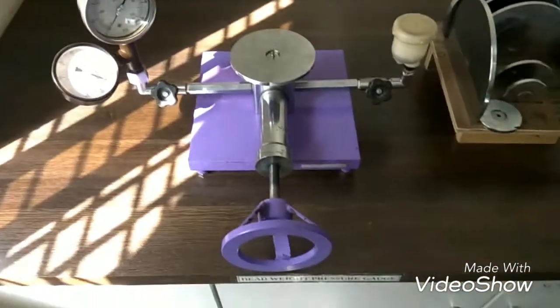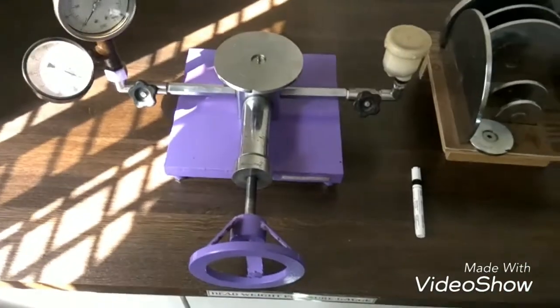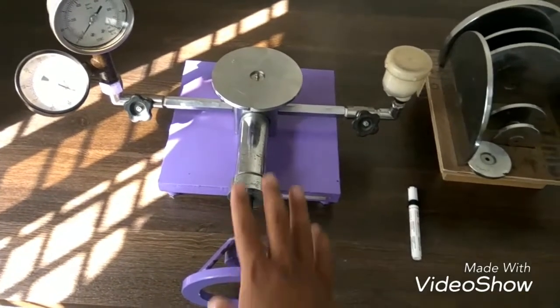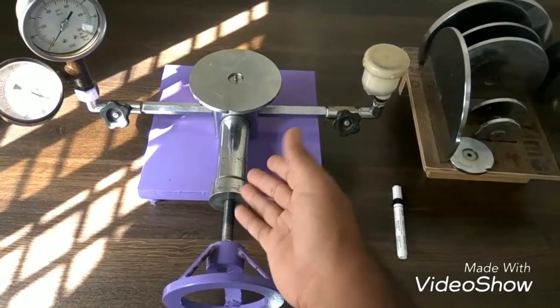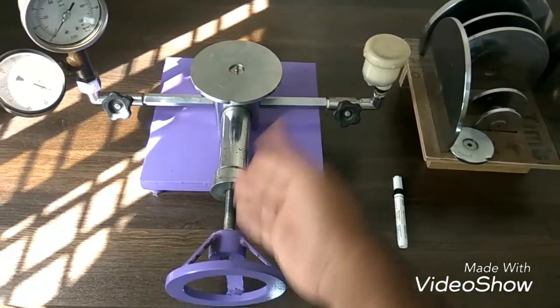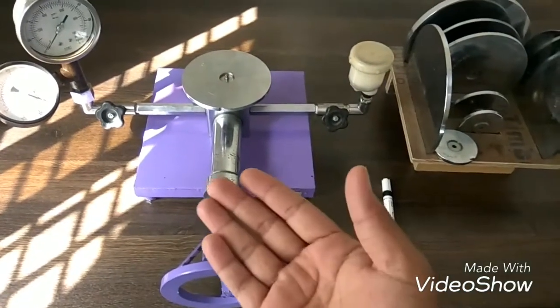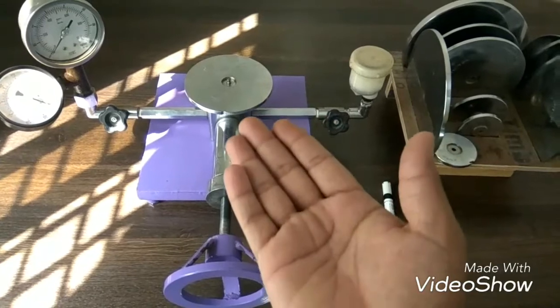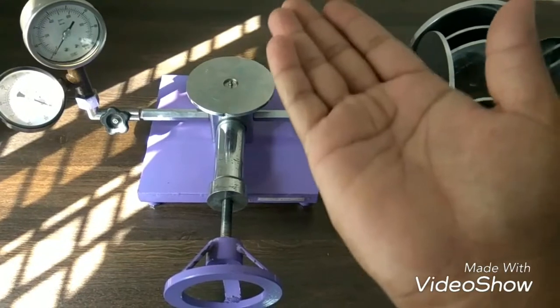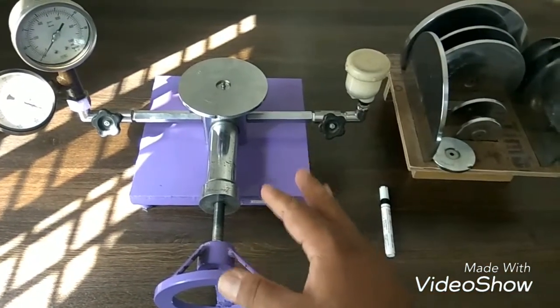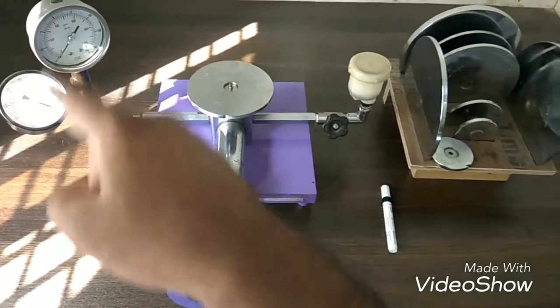Now, how it works - the basic working principle is whenever I apply pressure to the system through this handle, because of this pressure present in the system, this plate will start lifting in the upward direction. After some duration, if I am consistently applying pressure to the system, it will lift and float. The moment it starts floating, we can calibrate and measure the pressure using these two gauges.